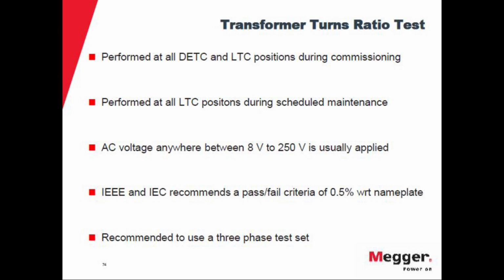Now you have to perform this on the 3 phases, so the ideal thing is to use a 3-phase test set that can facilitate the testing and allow you to perform a very quick test. Then you do the winding resistance test.